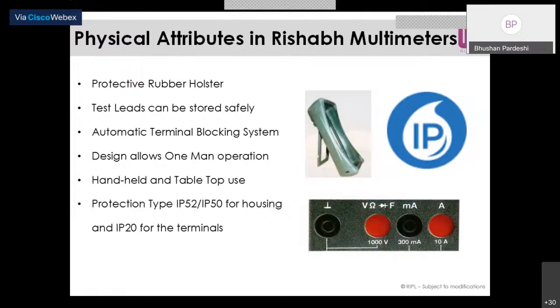And the last point is the protection type, that is ingress protection, known as IP52 ingress protection, IP50 for housing and IP20 for terminal. So I will just let you know in detail what IP52 indicates. In IP52, the first digit, that is 5, indicates protection against solids. So that is dust protected, limited ingress of dust is permitted and will not interfere with operation of the equipment. And the second digit, that is 2, indicates protection against vertically falling drops of water with the enclosure tilted up to 15 degrees from the vertical. That is, limited ingress permitted.